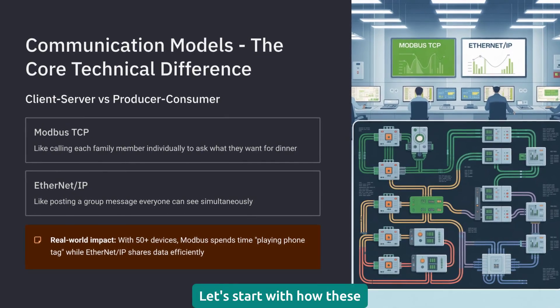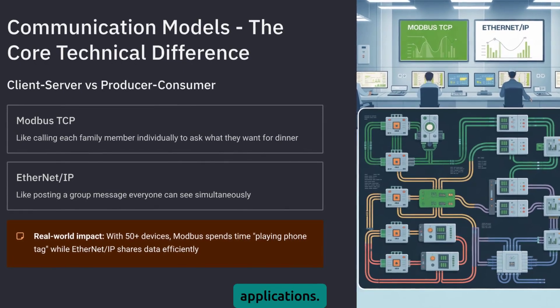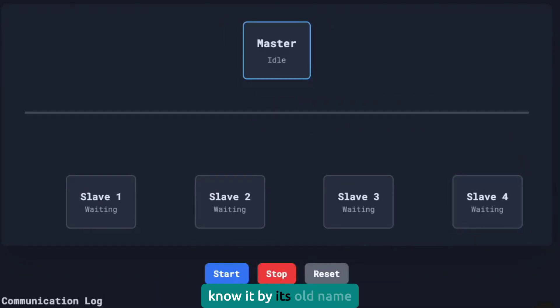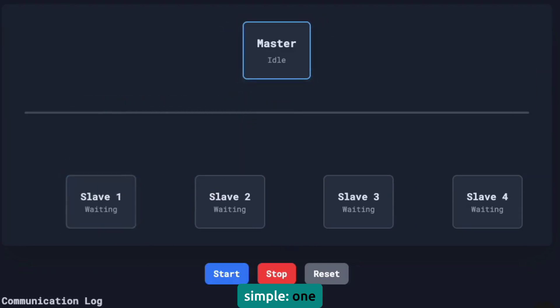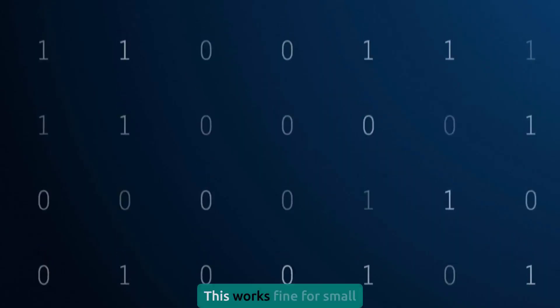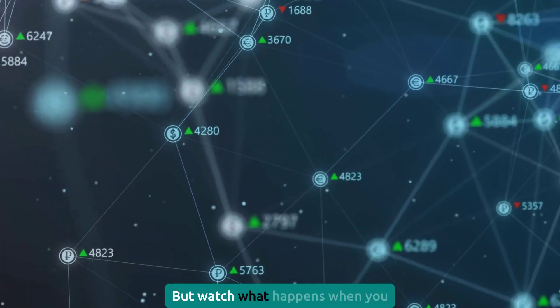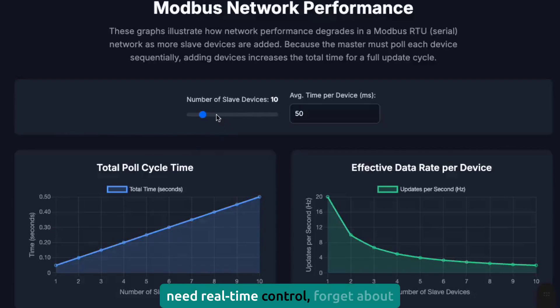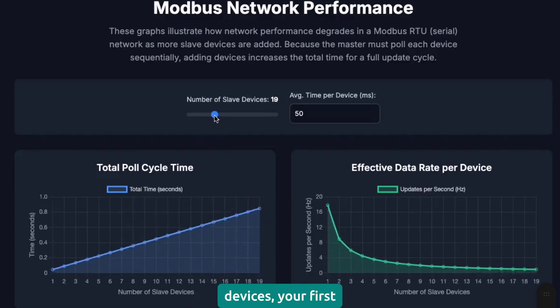Let's start with how these protocols actually communicate, because this is where the rubber meets the road in real applications. Modbus TCP uses what we call a client-server model, though you might know it by its old name, master-slave. The concept is simple: one device asks, another device answers — always. This works fine for small systems or when you're just monitoring data that doesn't change quickly. But watch what happens when you scale up. With 50 devices and real-time control needs, by the time you've polled all 50 devices, your first reading is ancient history.